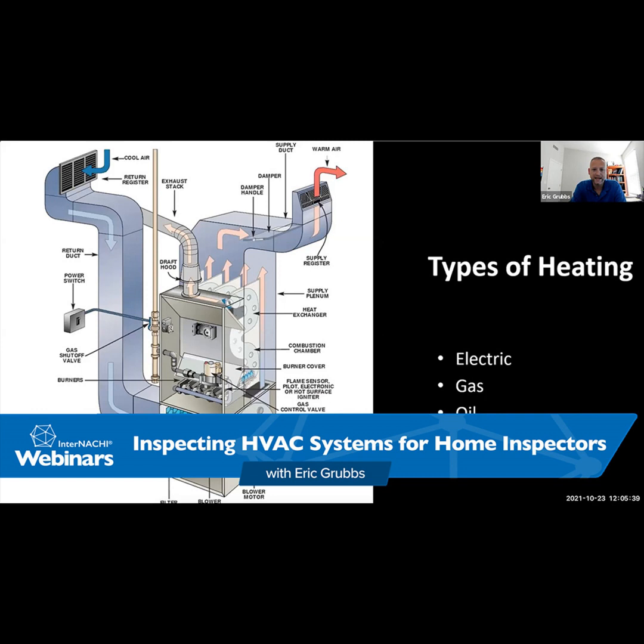One big difference between an oil-fired and a natural gas type system or propane system is that it has its own burner that's completely separate from the unit. Even though it's mounted onto the unit, this component right here, the gun type burner, actually does everything internal and produces the flame. So it has the oil pump, it has its own centrifugal fan to pull in mixed air, and then it also has its own igniter to ignite the air fuel combination, and then produces a flame on that.